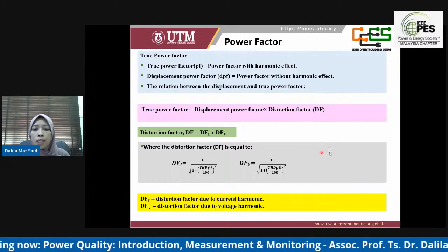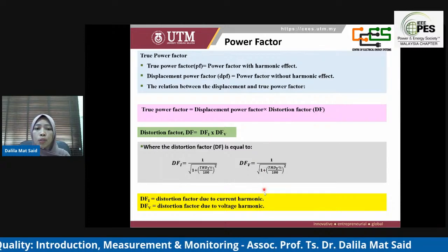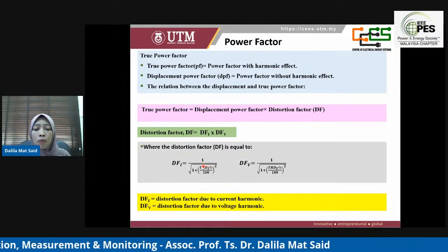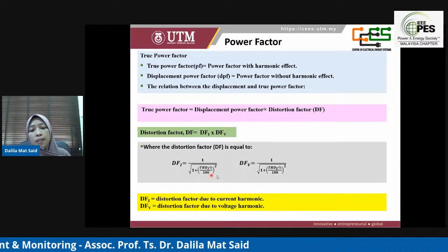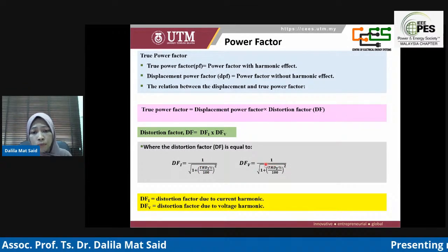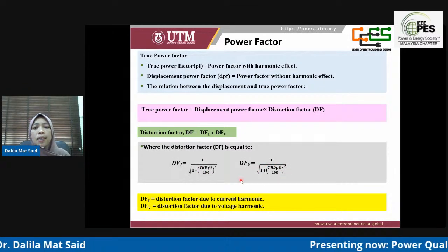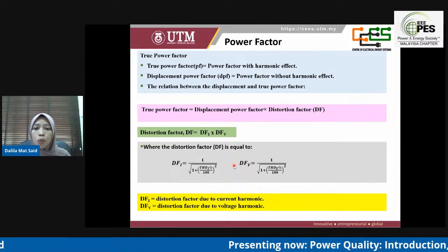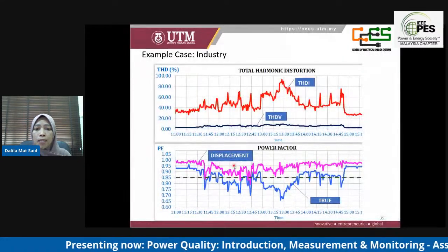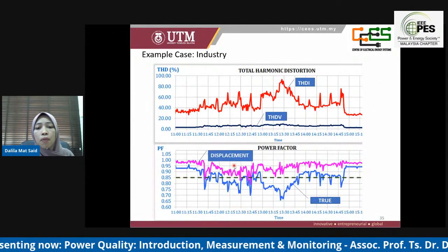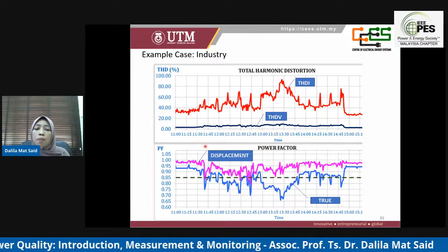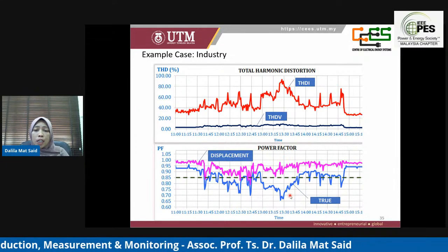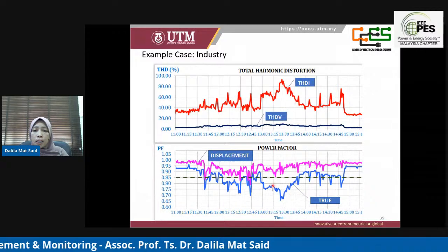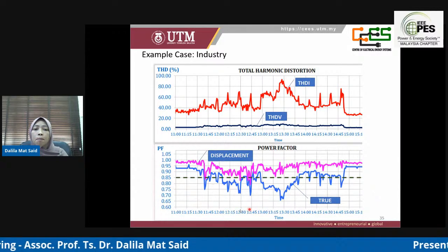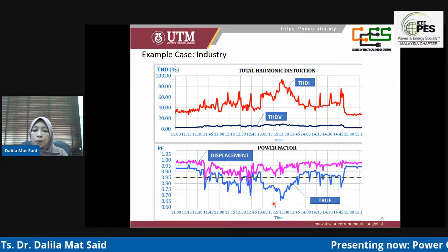And how do we get the distortion factor? We can use both the contribution of total harmonic distortion from current and total harmonic distortion from voltage to calculate the distortion factor, and we will get the value of the true power factor. So this is an example of harmonic data, both THDI for current and THDV for voltage, and the impact on the true power factor.